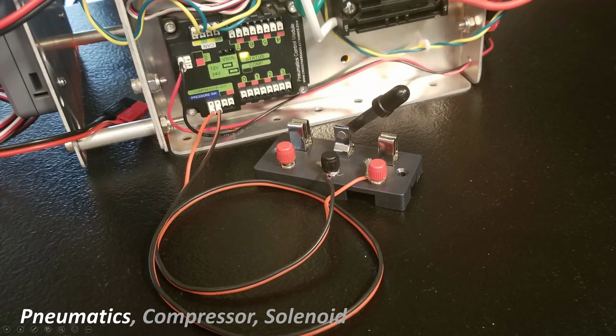We will emulate the pressure switch using this knife switch. The pressure switch determines whether or not you have low system pressure, and then the logic will turn the compressor on and off. The compressor power connects to these two pins right here. All solenoids must either be 12 volt coils or 24 volt. This one is set for 12 volts because of a connecting jumper right here. Power to the module is fed here off the power distribution board, the PDB.